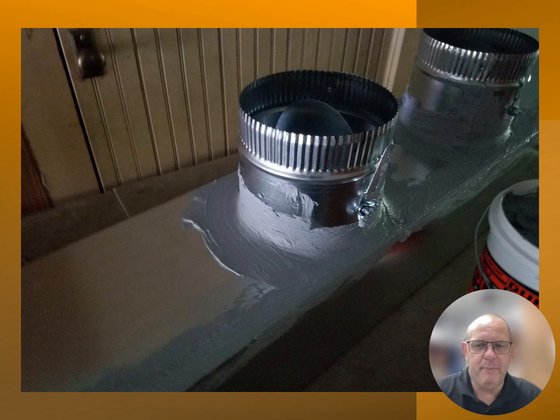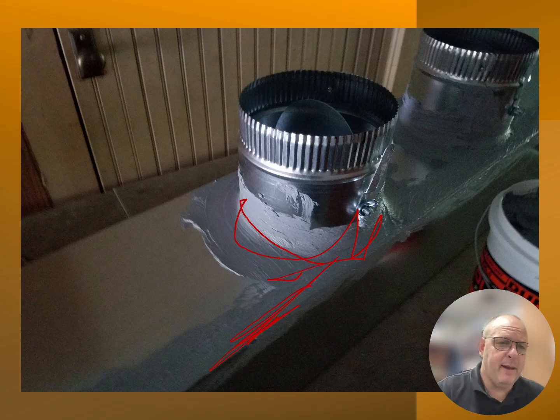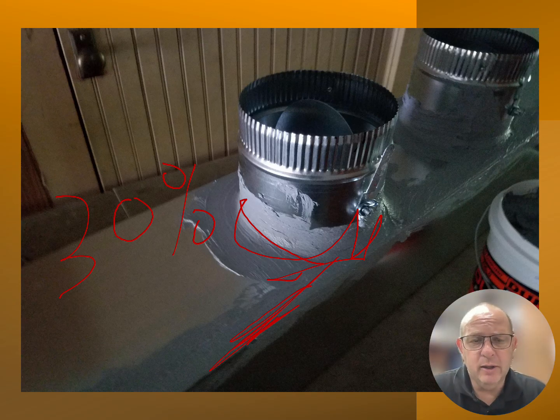Okay, so I painted that mastic onto that piece of ductwork, and you can see that I have done the seams of that ductwork on the square. I have done my takeoff, and I have gooped it on. I mean, I really want this ductwork to be sealed. Remember that 30% of your energy is actually going to be lost to air moving out of your ductwork. And we want to try to keep that air within the ductwork.